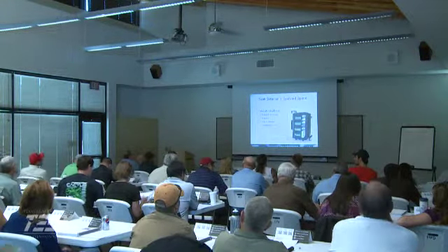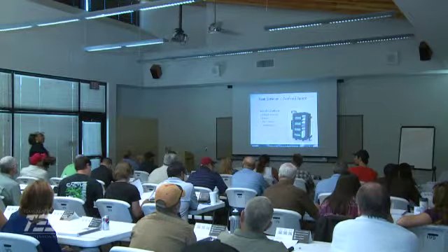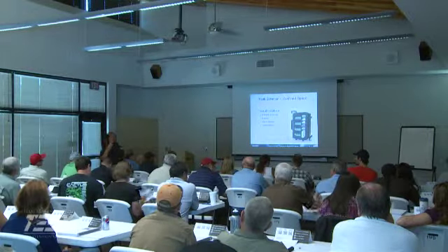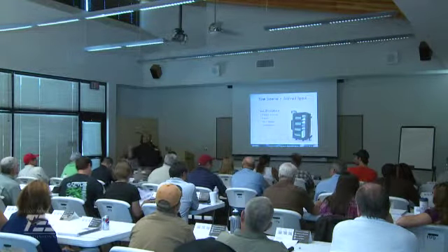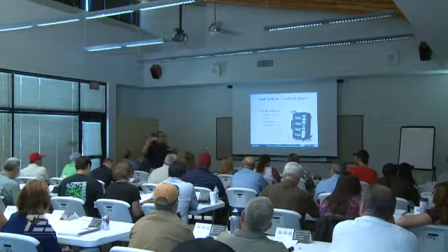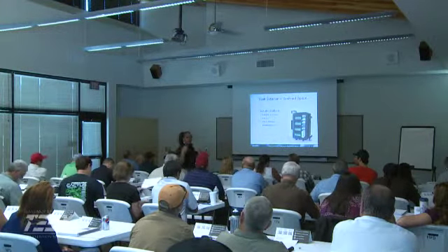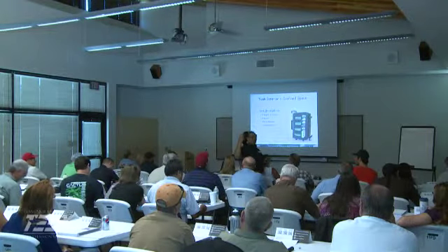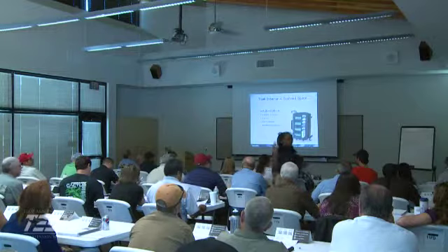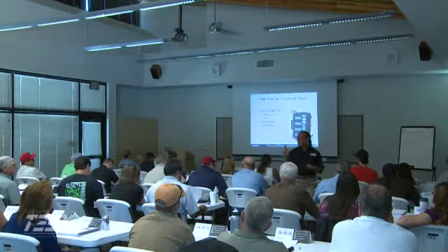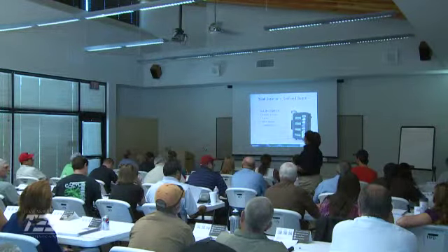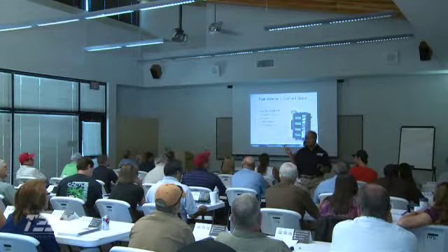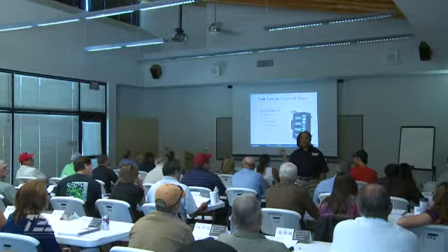Anything that's explosive, combustible. And then I will test for toxic, because 9 times out of 10 when you're looking at, I heard hydrogen sulfide was one of the ones. Again, it may be toxic before explosive, but methane's going to get us before that toxic gas. So oxygen, combustible, and then we're going to test for the toxic gases. So you gave me oxygen, you told me methane was combustible, and I guess hydrogen sulfide is the toxic one.